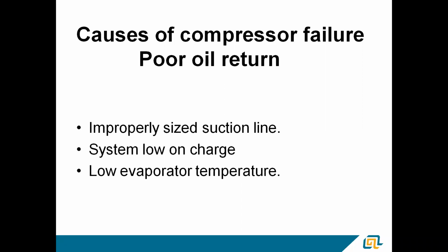Poor oil return. This is another cause of compressor failure. Improperly sized suction line. If your suction line is too big, you won't have enough velocity to bring the oil back to the compressor. One thing I always mention is to be careful when you're reusing existing line sets, especially if it was an old R22 system and now you're putting in R410A. R22 suction lines were sized larger than R410A should be. So there may be times when you're putting in a new R410A system, that suction line is too big and you'll have poor oil return. You might start fighting compressor failures. System low on charge. If it's low on charge, again, there isn't enough suction gas coming back to the compressor to bring our oil back.